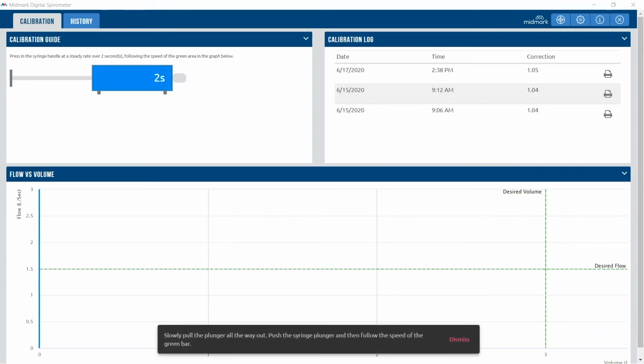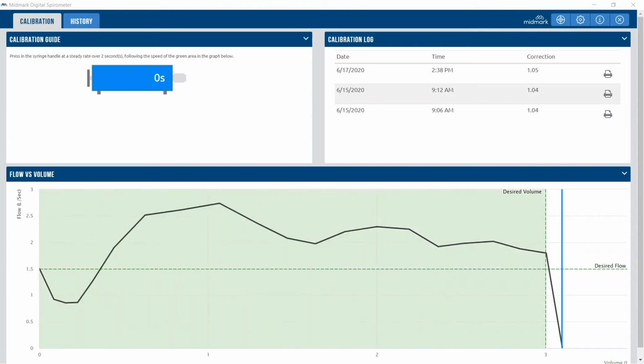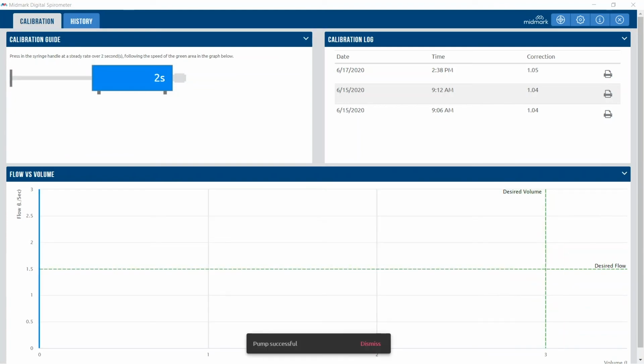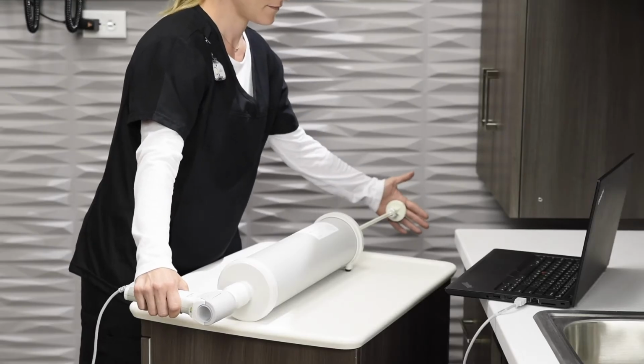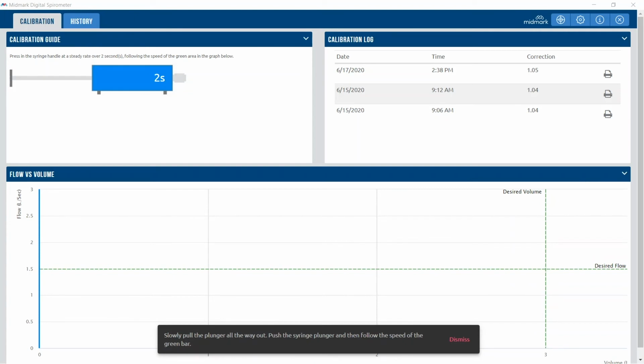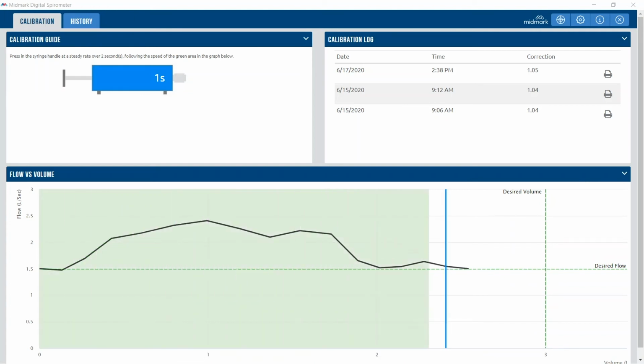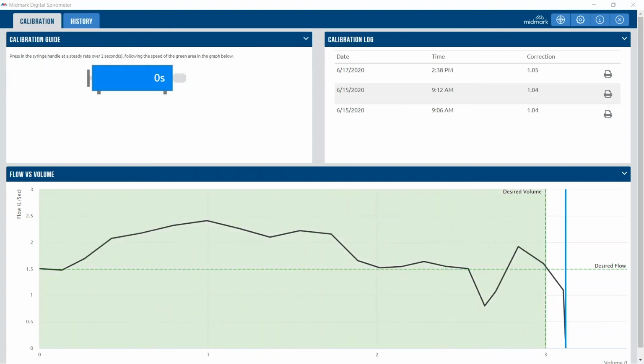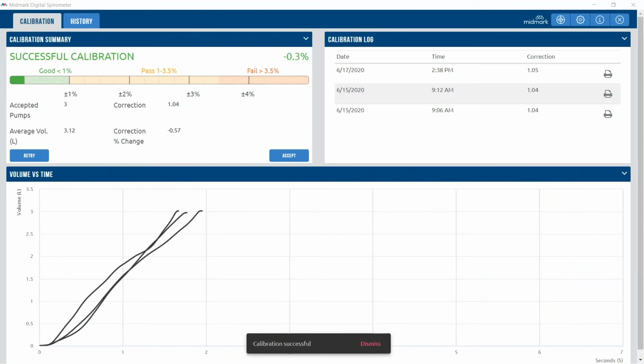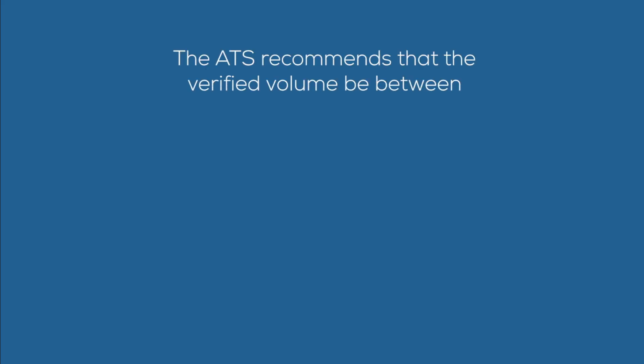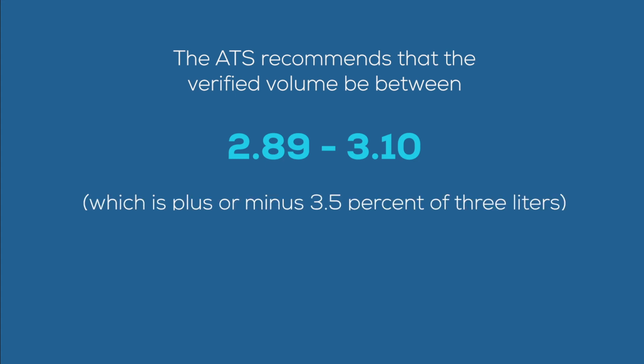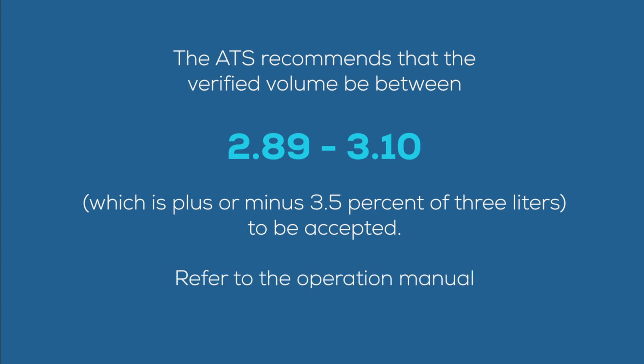After 3 correctly performed calibration checks, the system will automatically calculate a correction factor and prompt you to perform 1 verification pump. The spirometer will display a pass or fail message once the calibration procedure has been completed. The ATS recommends that the verified volume be between 2.89 and 3.10, which is plus or minus 3.5% of 3 liters, to be accepted. Refer to the operation manual for further detailed instructions.